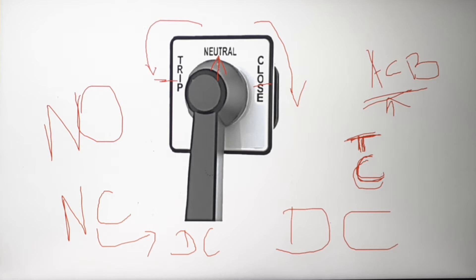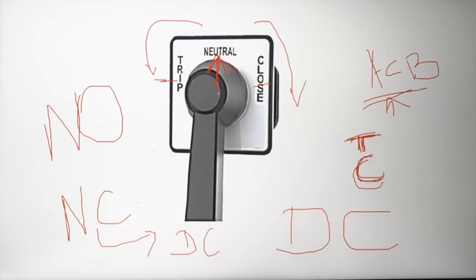Similarly, if I rotate the knob towards the trip position, initially that contact is normally open. When I rotate to the trip position it becomes normally closed, allowing the DC supply — about one second or less — to energize the trip coil. After operating, the knob automatically returns to the default neutral position due to a spring mechanism inside the TNC switch.